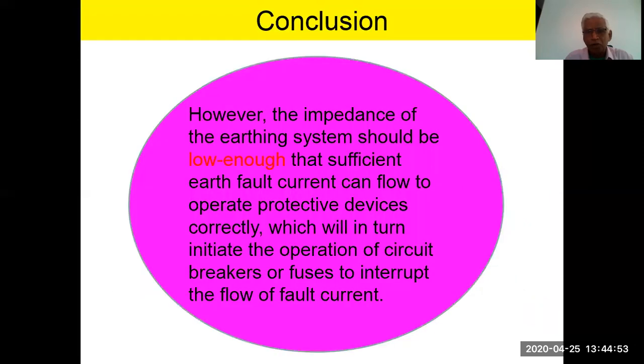And conclusion: however, the impedance of the earthing system should be low enough that sufficient earth fault current can flow to operate the protective devices correctly, which will in turn initiate the operation of the circuit breakers or fuses to interrupt the flow of the current.